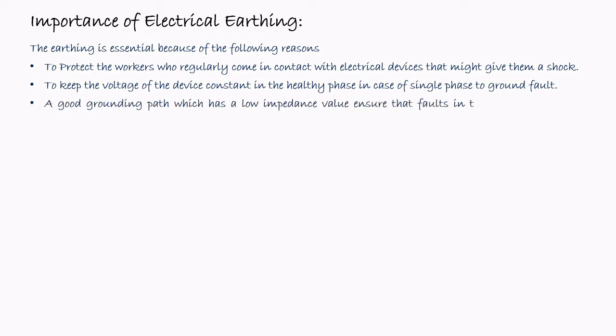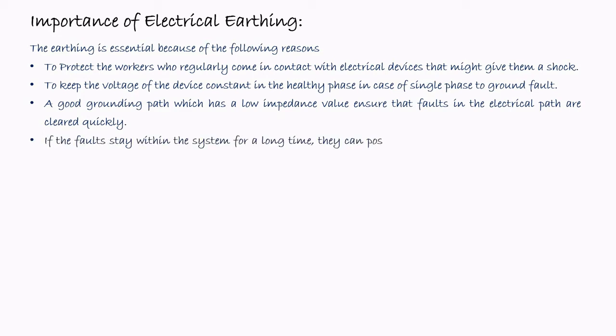A good grounding path which has a low impedance value ensures that the faults in the electrical path are cleared quickly. So if there is any fault, by using the earth leakage circuit breaker, we can identify the fault and then it can be easily cleared and the system can be restored again. But for that, the fault current should pass to the earth wire so that there should not be any damage or any accident. Now, if the faults stay within the system for a long time, they can pose a serious threat to the stability of the system.